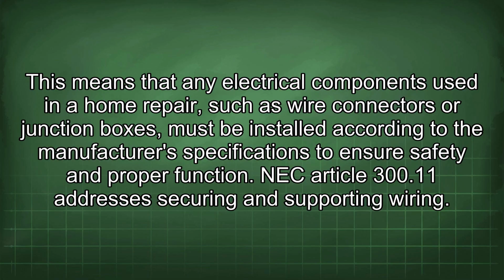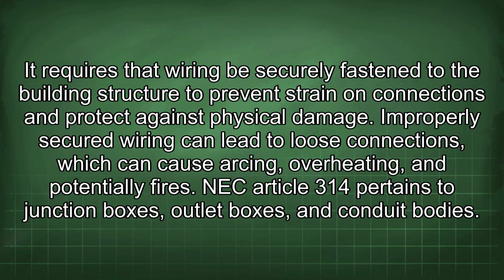NEC Article 300.11 addresses securing and supporting wiring. It requires that wiring be securely fastened to the building structure to prevent strain on connections and protect against physical damage. Improperly secured wiring can lead to loose connections, which can cause arcing, overheating, and potentially fires.